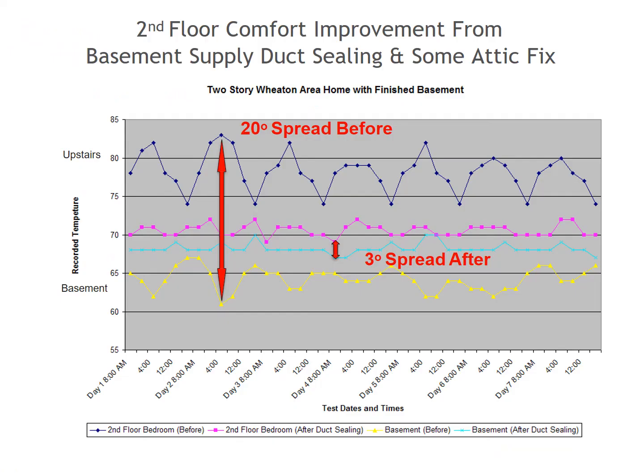What you're looking at here is an actual report from a 2-story home with a finished basement. And what you're seeing is you can see the blue line go up and down, up and down. That is the upstairs portion of this home that fluctuated greatly because there was a lot of duct leakage. The pink line directly below it, you can see how not only were they able to drop the temperature in the house by fixing the duct leakage, they are also able to minimize how much the air temperature actually jumped up and down over a period of time. Same thing happened in the basement when you look at the yellow line versus the teal line.